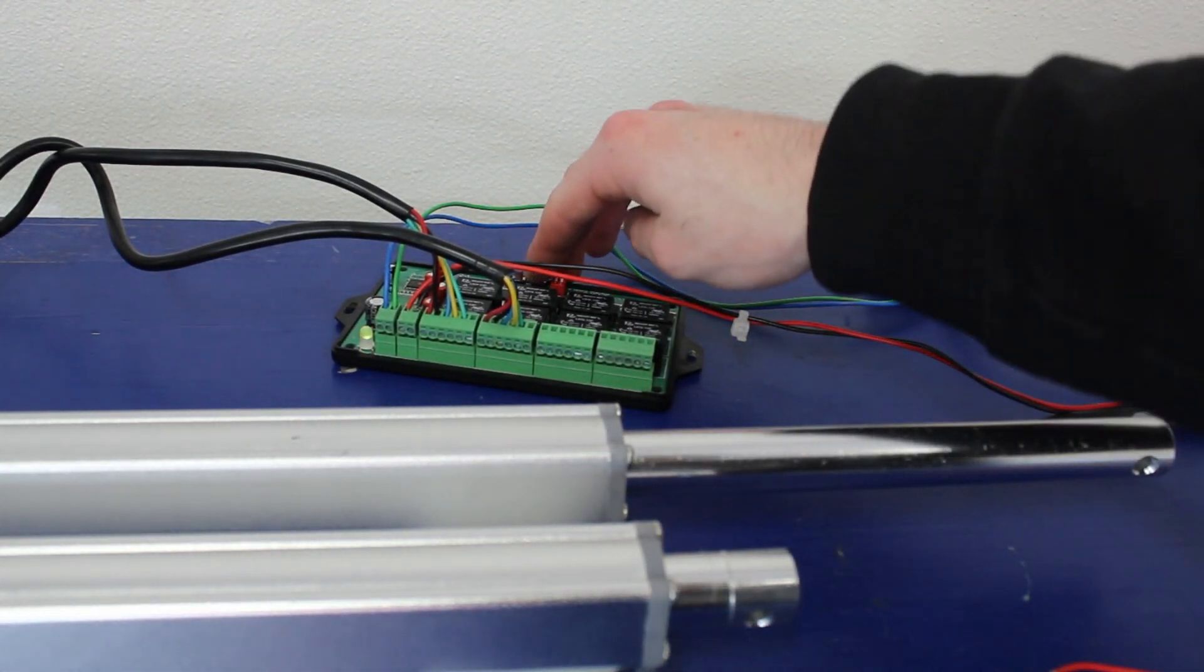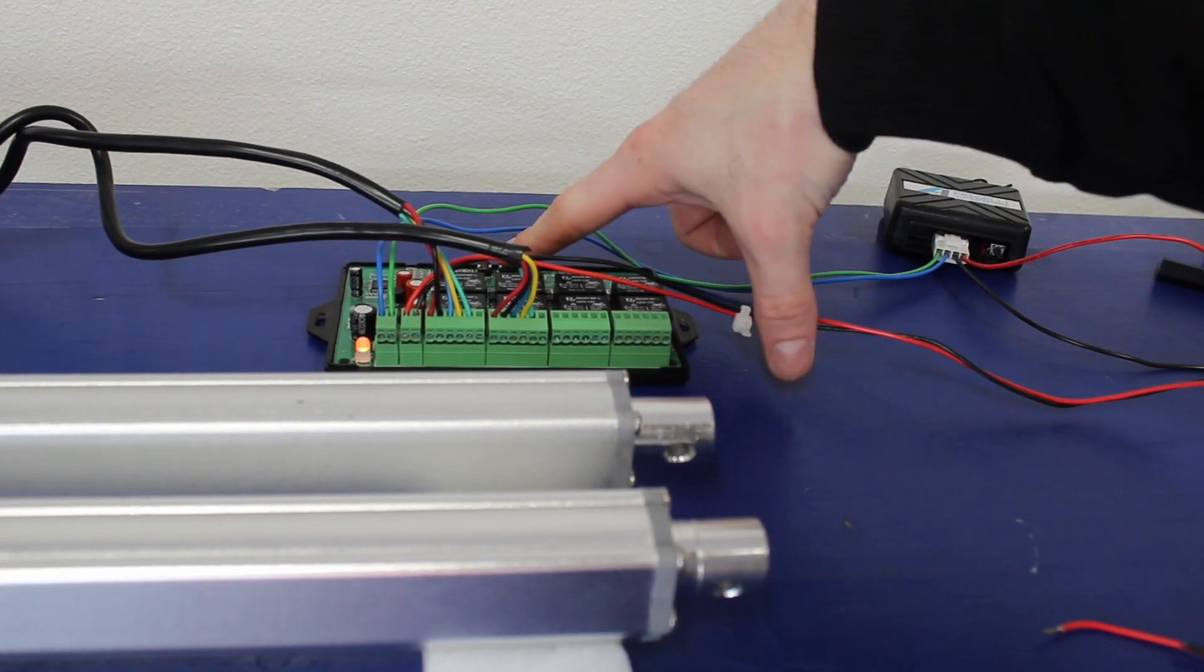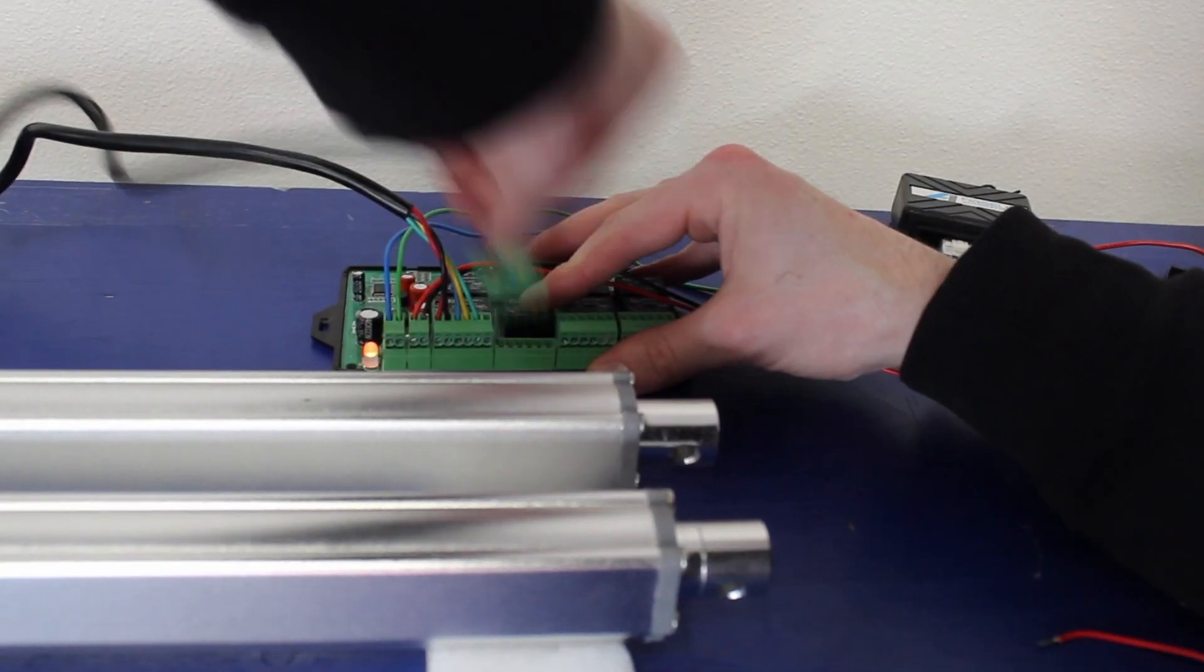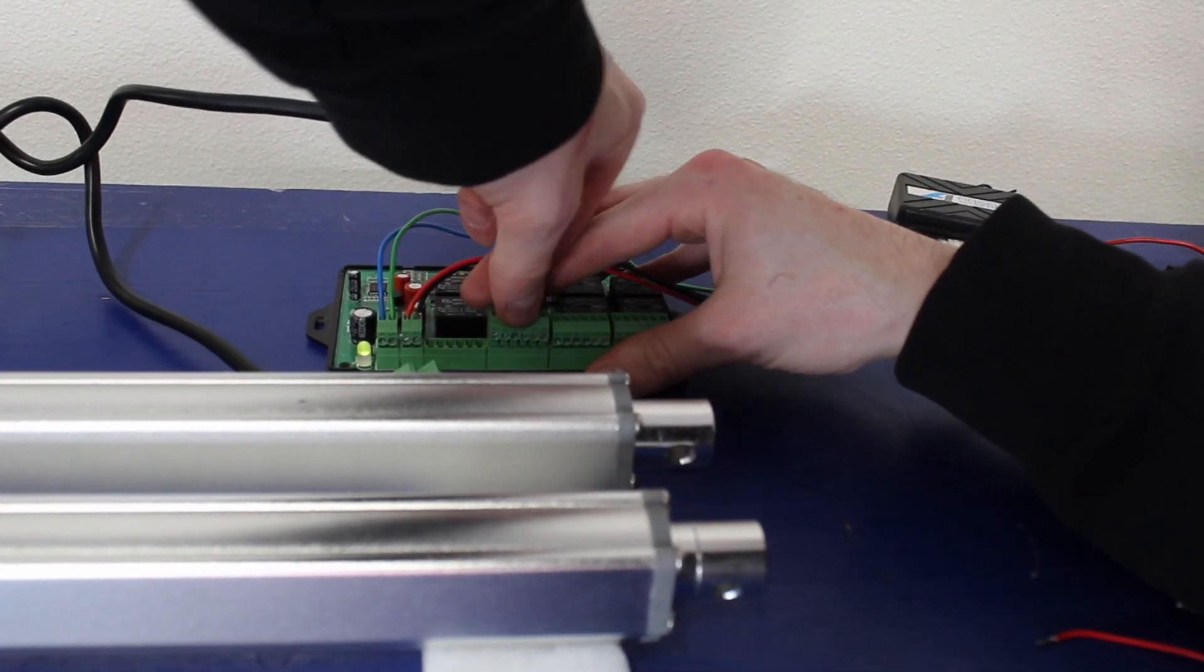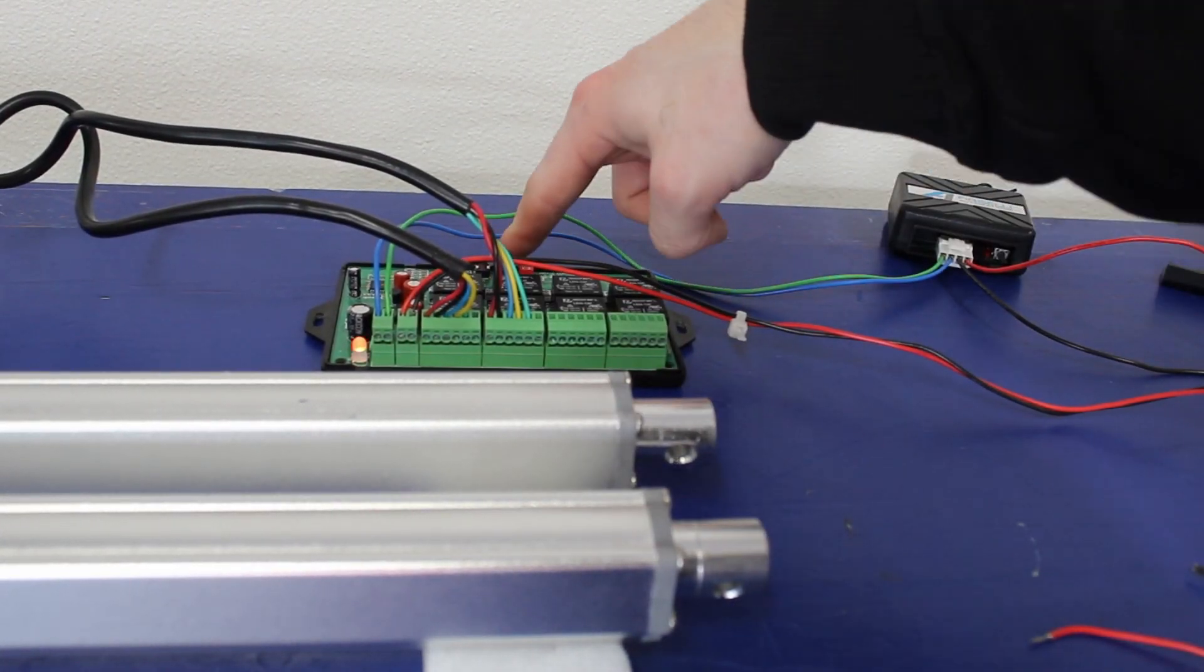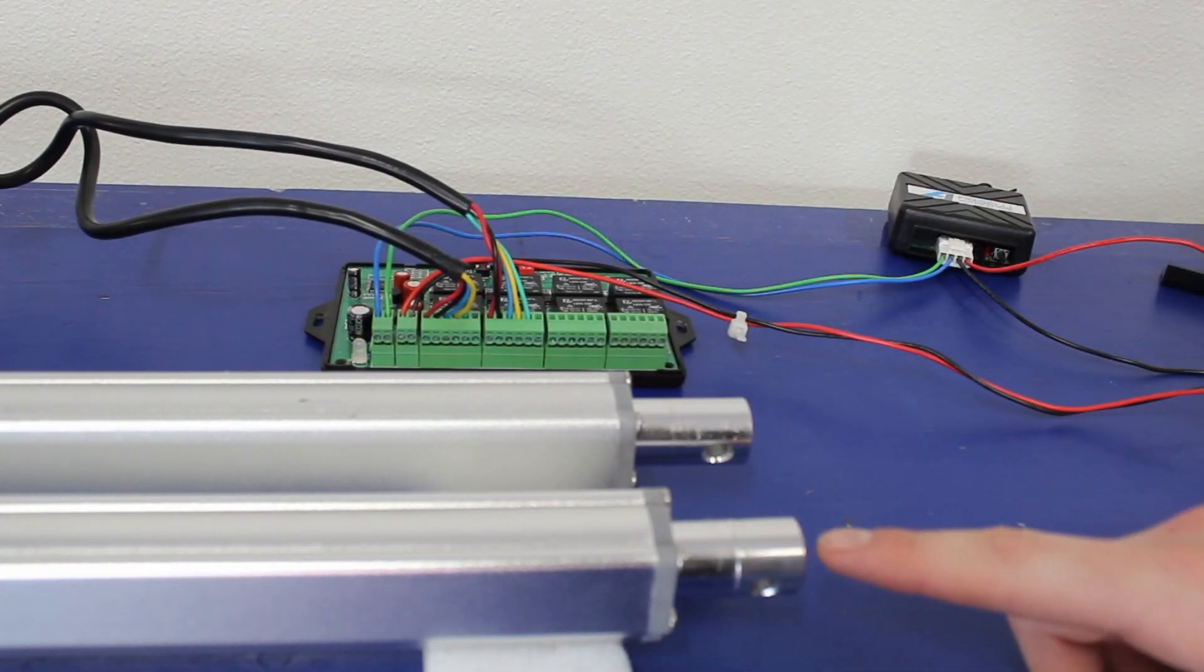Bringing them both back home, what I'm going to do here, recheck the wires, switch the carriage positions relative to the sync box. So now that actuator is in position one. See? There we go. And run the calibration again, and the same actuator stopped, which tells me that it is that actuator, not the other one.